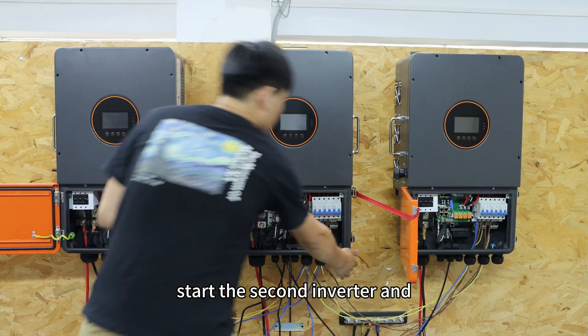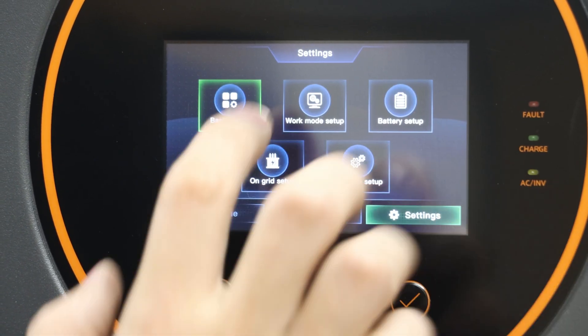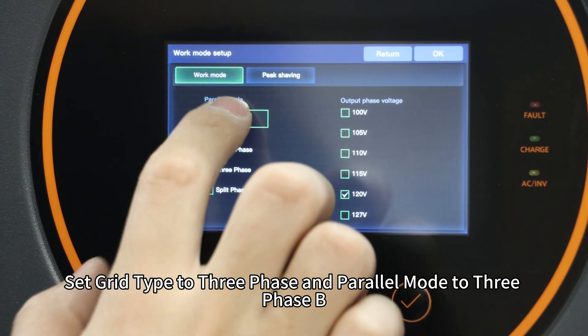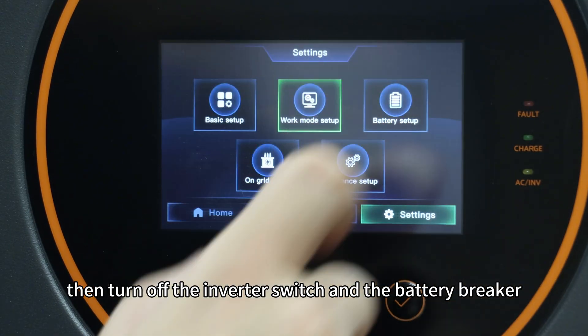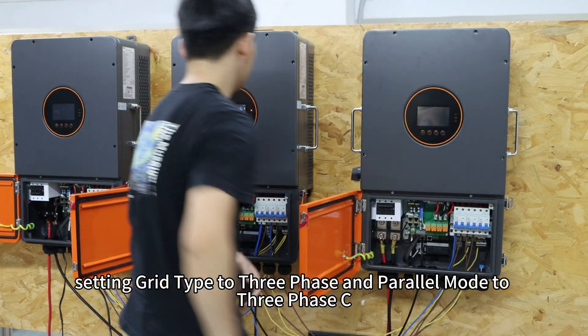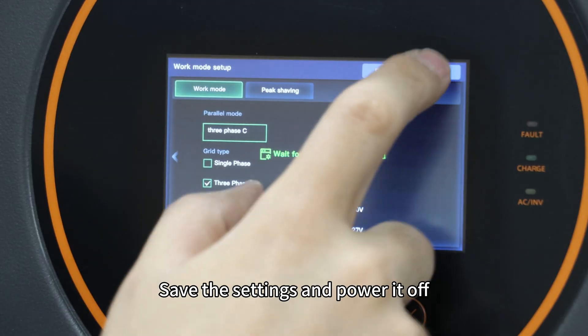Next, start the second inverter and before it begins inverting, go to the same work mode setup page. Set grid type to 3-phase and the parallel mode to 3-phase B. Click OK to save, then turn off the inverter switch and battery breaker. Repeat the same steps for the third inverter, setting grid type to 3-phase and the parallel mode to 3-phase C. Save the settings and power it off.